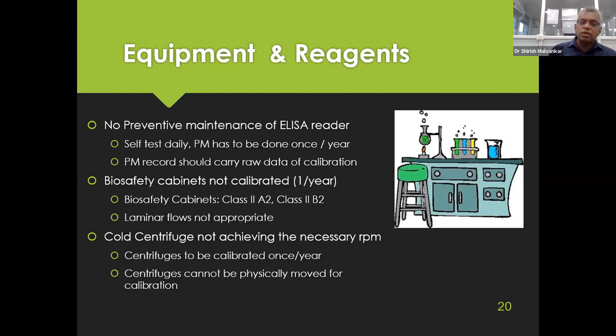The cold centrifuge not achieving necessary RPM. Now, a centrifuge again needs to be calibrated once a year. Centrifuges obviously cannot be physically moved for calibration. So someone with a calibrated tachometer needs to visit the laboratory and do the centrifuge calibration on site. And preferably the instrument should not be moved after that at all. If you happen to change the position of the centrifuge, please understand that you need to recalibrate the equipment in the new position.